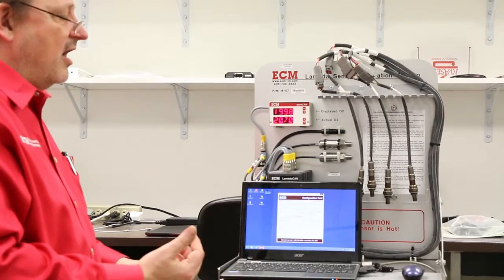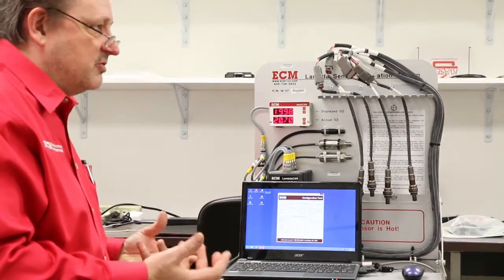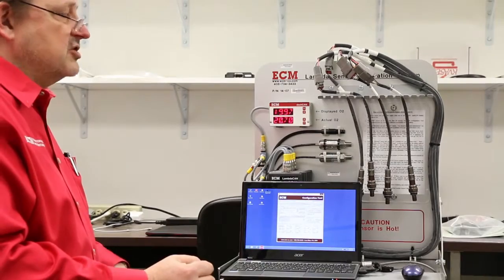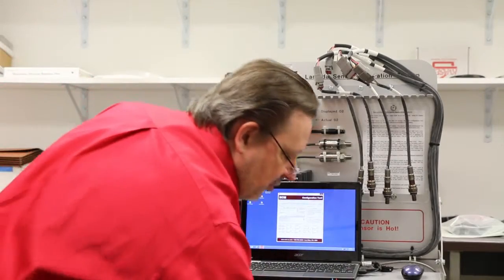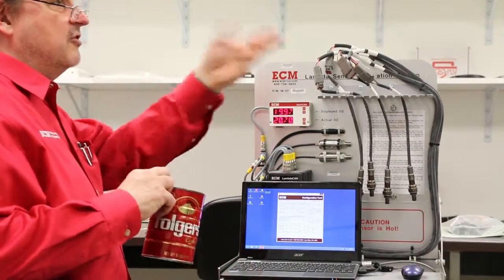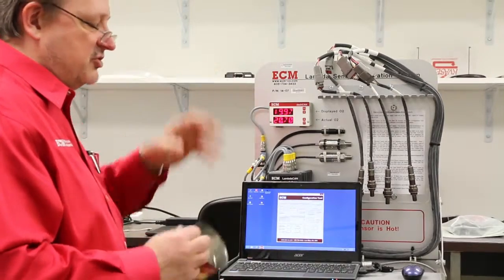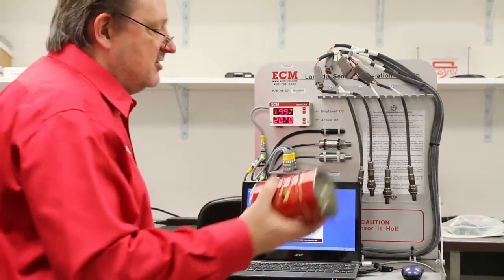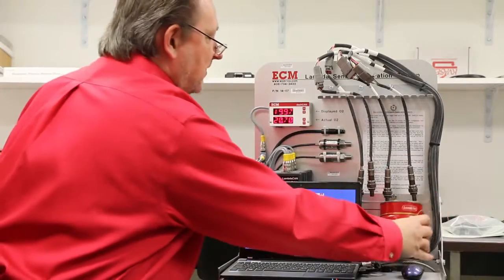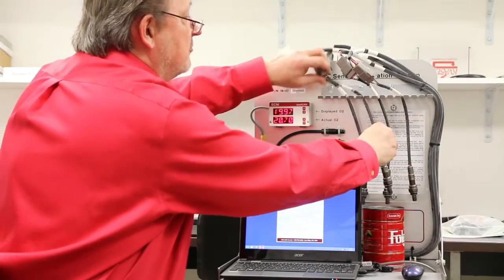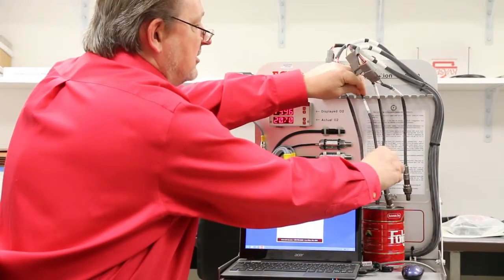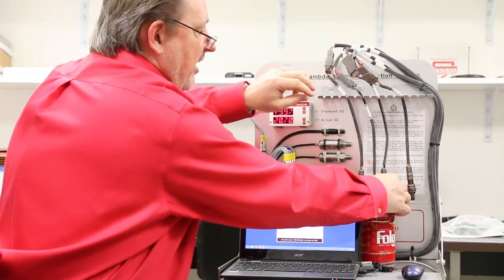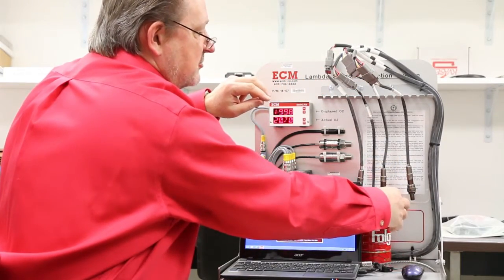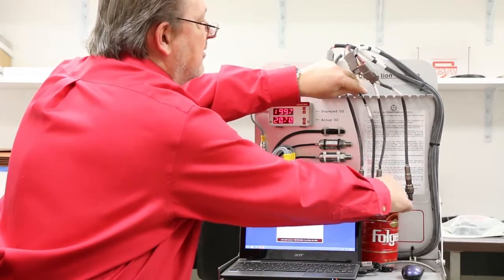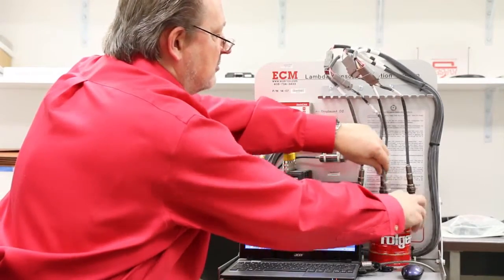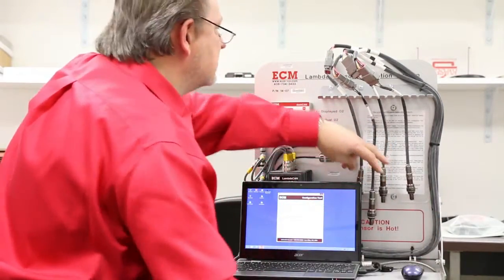And so after one hour, or after they stop smelling, which will be longer, you're going to span the sensor in the room air. But if you have a lot of wind in your room, it's going to make the calibration numbers jumpy. So what you can do is take a can like this, a clean one. Don't want to have one that's oily, because if you can smell oil or gasoline in there, the sensor is not seeing pure air. And then hang the sensor or sensors in there just to keep the wind off it. But in this case, we don't have any wind, so we're not going to need this can.